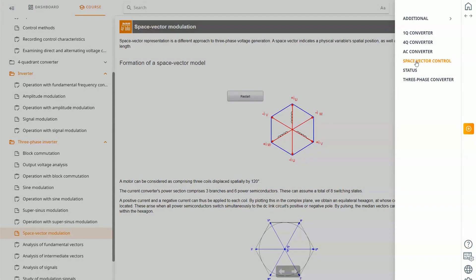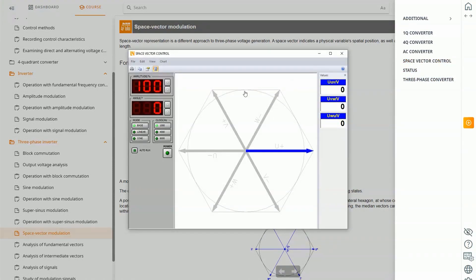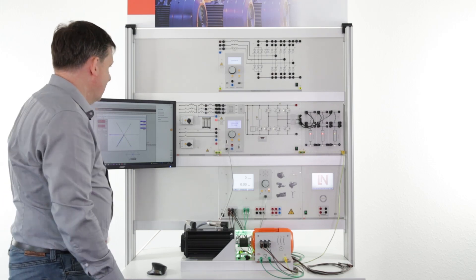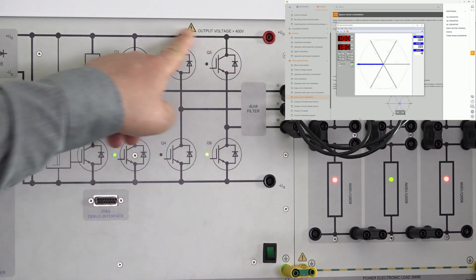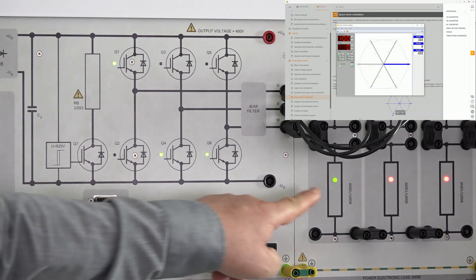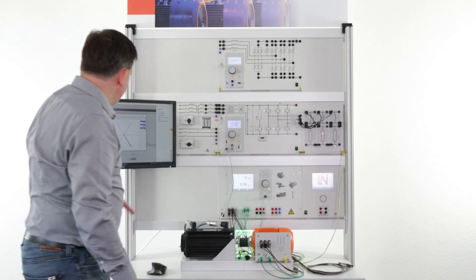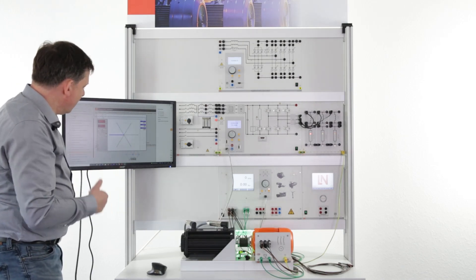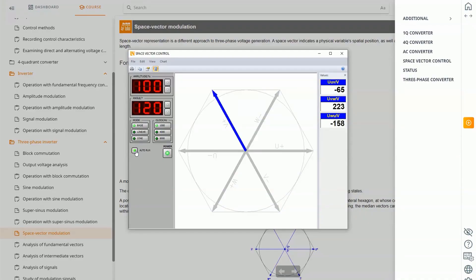For this purpose, to understand how it works, we developed what we call a virtual instrument — the space vector control instrument. When I open it and press power, the IGBTs get power. If I press the auto button, you see that we now apply a sequence to our frequency converter. With this sequence, the load gets powered, and this sequence — you can imagine with the angle here — will turn the motor. At the moment, we have six stages which are turning the motor, so the motor will click, click, click.